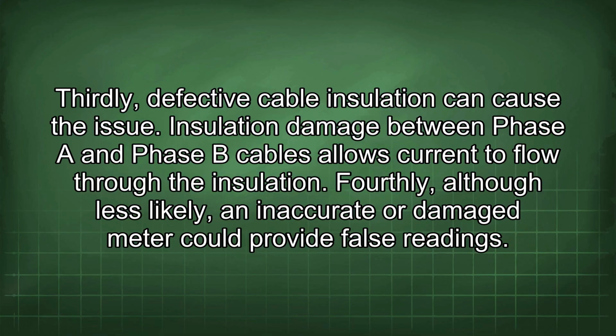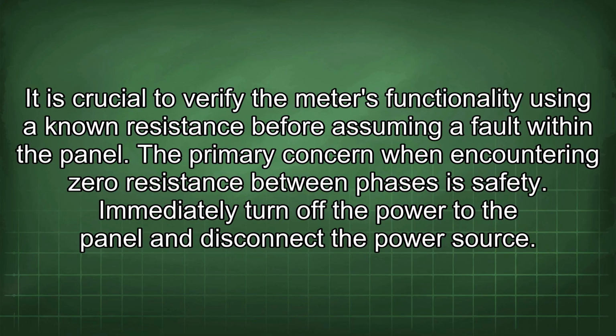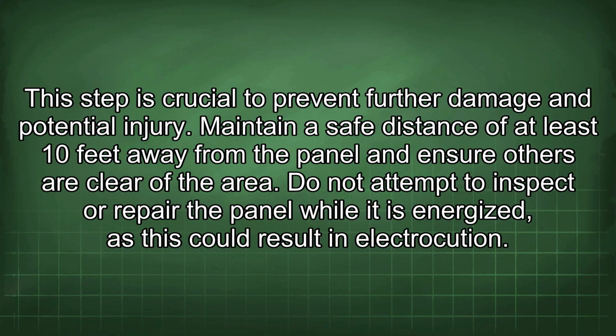Fourthly, although less likely, an inaccurate or damaged meter could provide false readings. It is crucial to verify the meter's functionality using a known resistance before assuming a fault within the panel. The primary concern when encountering zero resistance between phases is safety. Immediately turn off the power to the panel and disconnect the power source. This step is crucial to prevent further damage and potential injury.